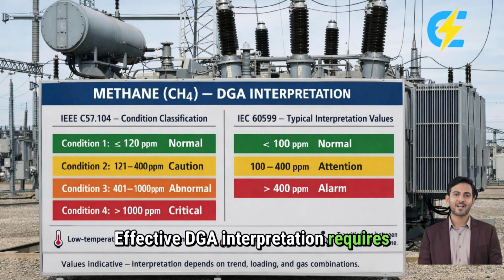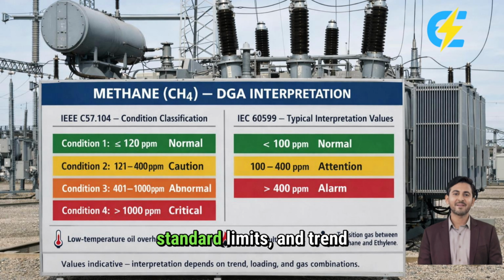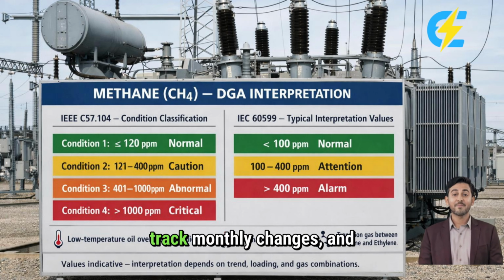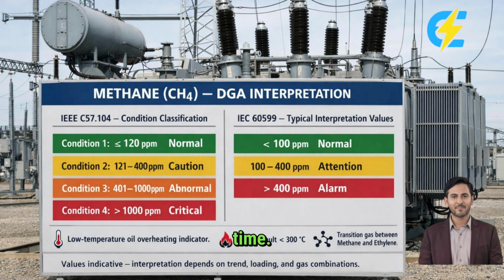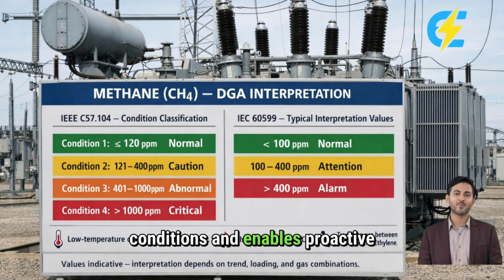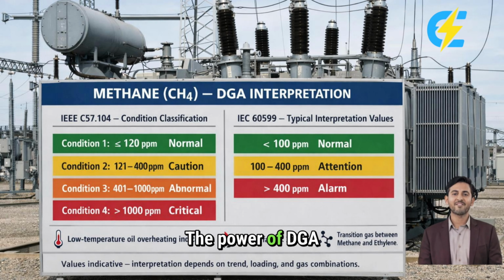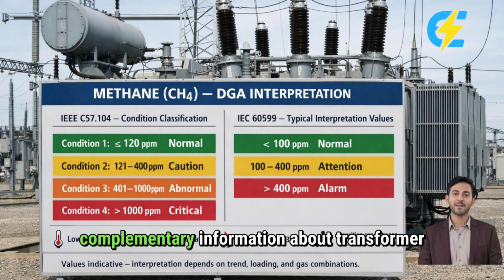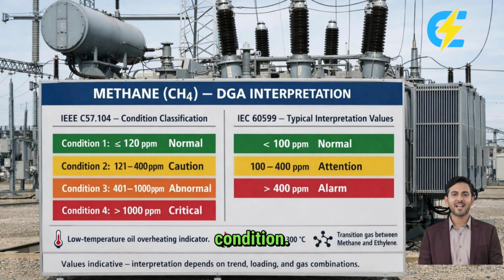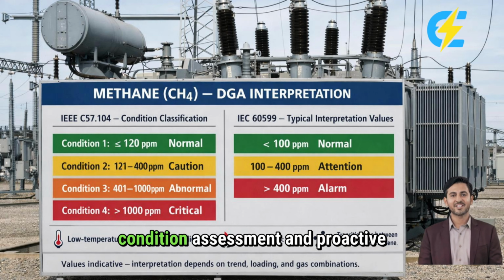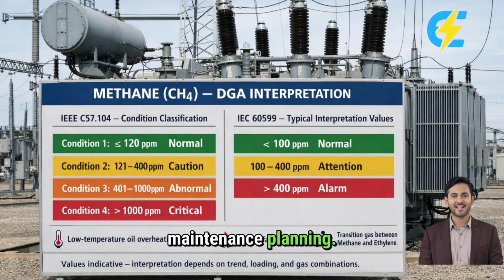Effective DGA interpretation requires understanding gas generation mechanisms, standard limits, and trend analysis principles. You must establish baseline conditions for each transformer, track monthly changes, and analyze gas patterns over time. Single-point measurements provide limited information. Trend analysis reveals developing conditions and enables proactive maintenance decisions. The power of DGA lies in early detection and appropriate action. Hydrogen and methane provide complementary information about transformer condition. Hydrogen reveals electrical stress development. Methane indicates thermal stress progression. Together, they enable comprehensive condition assessment and proactive maintenance planning.